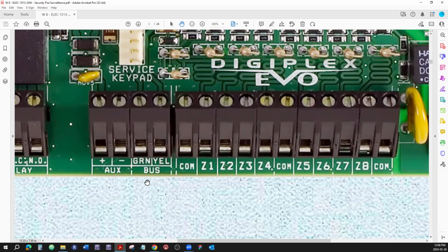So if you have a keypad connected, you'd have 4 terminals on the keypad: the power, which you connect, and the bus signal terminals, labeled green and yellow. You connect those and the keypad works. The next keypad you connect exactly the same way, and everything is in parallel because the signal is the bus. Different modulation techniques are used so the keypads can communicate individually with the main board while still being on the same bus signal-wise. It's basically just a parallel connection from one keypad to another, to another, to another.